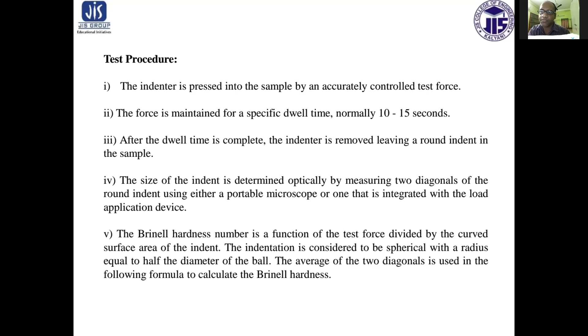The drawbacks of this Brinell hardness test are, first of all, the large size of the ball and high loads, so impressions are larger. These impressions may decrease the useful life of the component. The ball indenter is likely to deform while testing hard materials. This increases the diameter of the impression and gives a lower hardness number. Thin materials cannot be tested because of large depth penetrations.